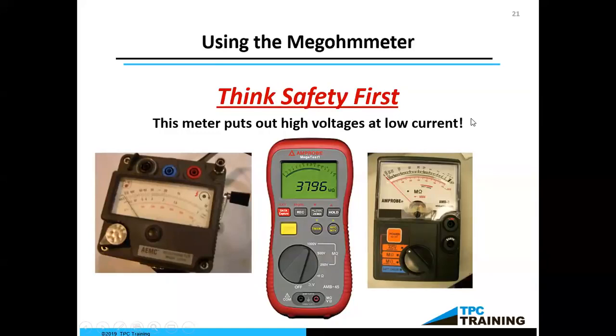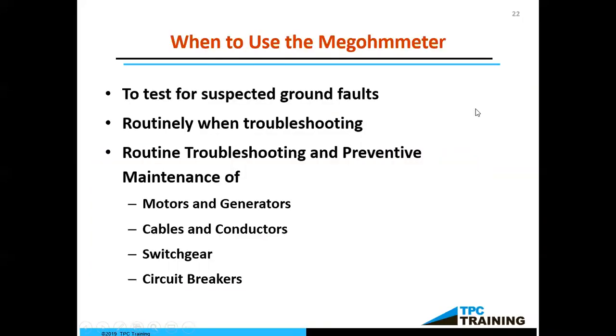And the other thing that this really allows us to do is make a good prediction of when that motor might fail. So it's just a great tool. It's something that we should routinely do. Many people do this semi-annually. Some people will do it annually, but it is going to test for a ground fault, which means, did my insulation deteriorate to the point where one of those bare wires is now hitting the frame of the motor? So that's what we're looking for, to see the quality of the insulation. We can do this on motors or generators, anything that has insulation on it, basically. But we're going to be using it, of course, on motors.